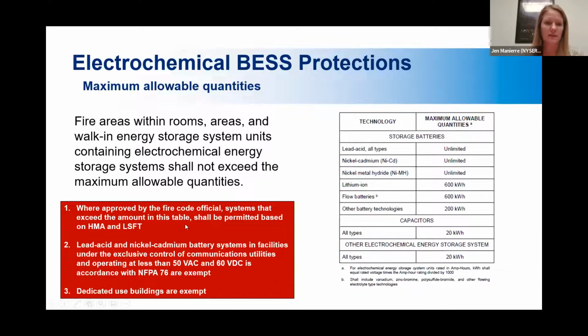And like I said, there are some exceptions throughout the code, and you can see them in this red box on the left here. So the first example is an exception to this maximum allowable quantities. Where approved by the fire code official, systems that exceed the amount in the table can be permitted based on the hazard mitigation analysis and large scale fire testing. So if they pass the test, you can do more than 600 kilowatt hours. And there are some other exceptions throughout the code as well.